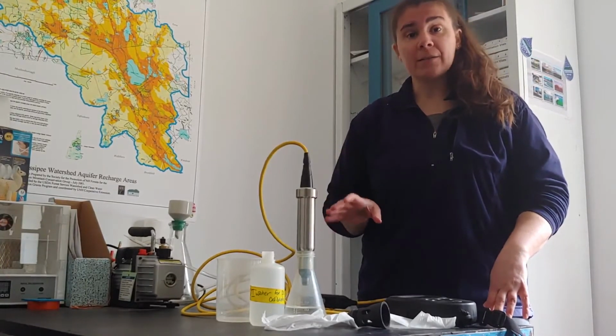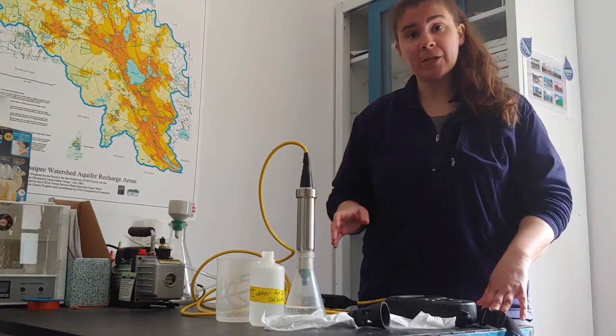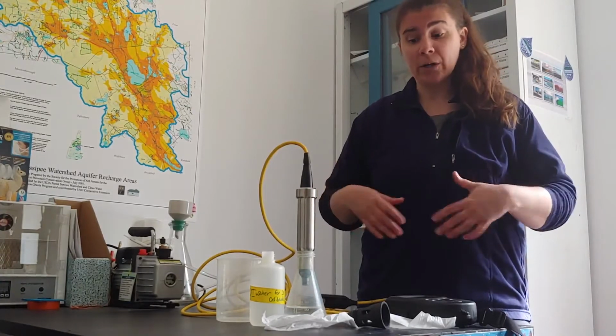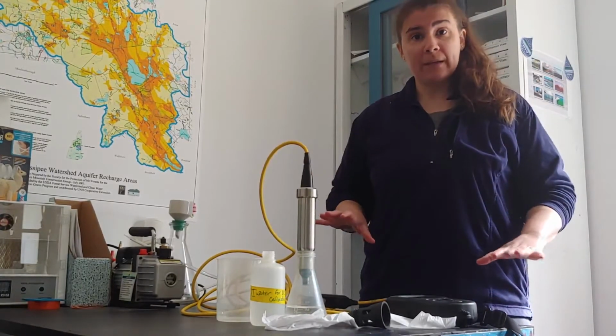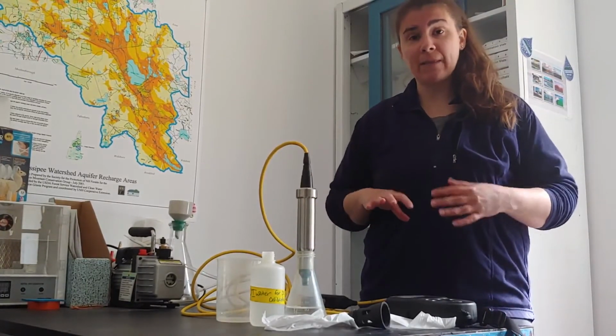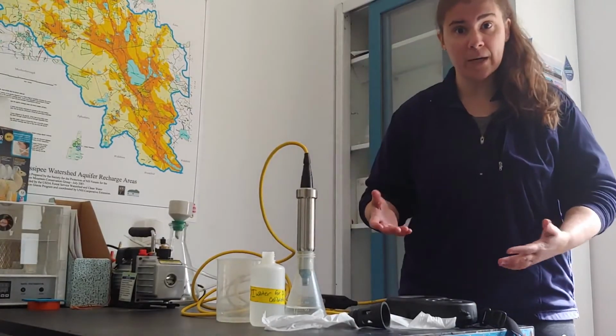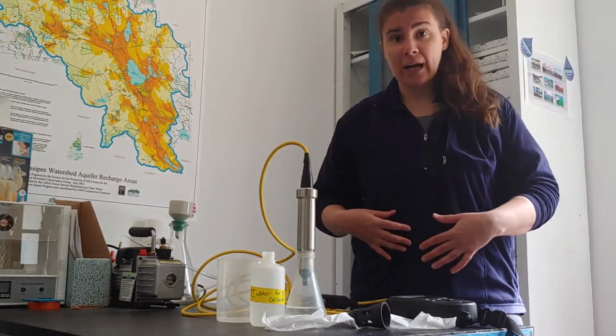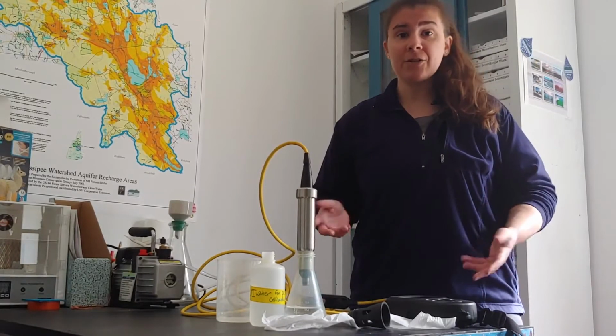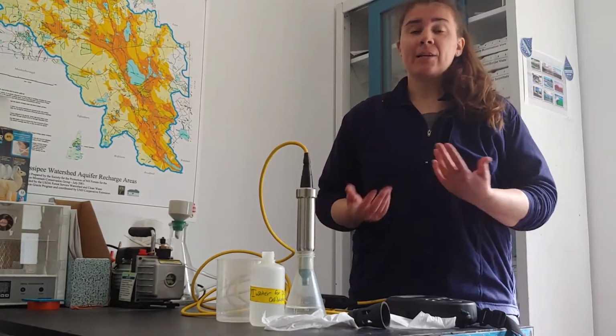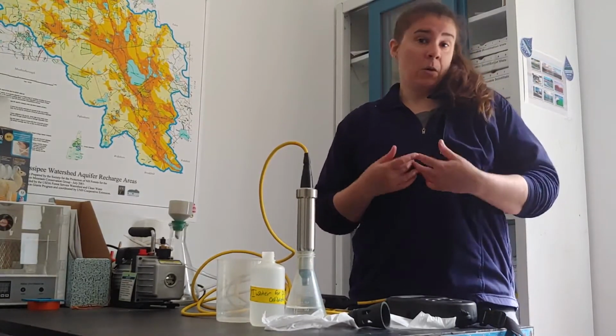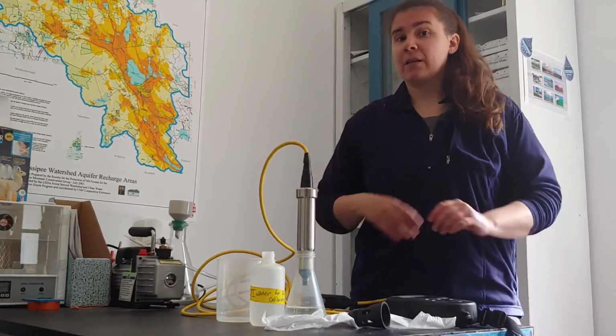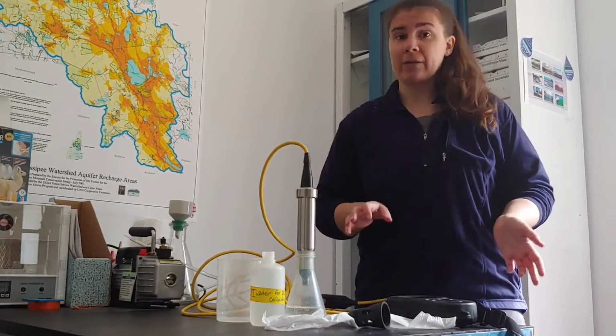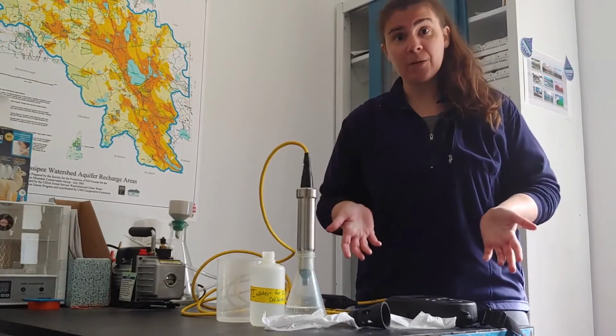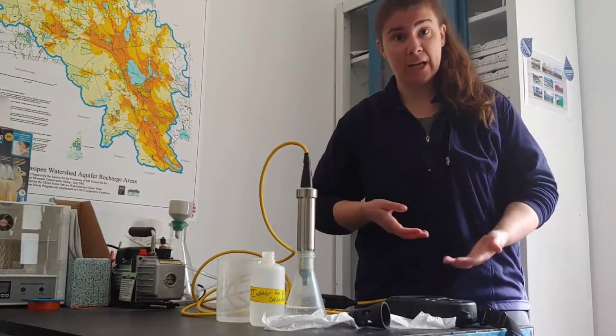A very important thing to keep in mind as you're doing this calibration is that it's easier and works faster if all the equipment is the same temperature. So we highly recommend that you do this calibration first thing in the morning. You bring the equipment into your house and you just calibrate it right in your kitchen or in your living room. I tell my volunteers a lot of times, just when you wake up, start your calibration and then go ahead and have your cup of coffee, eat your breakfast, brush your teeth, whatever it is you normally do in the morning, and then just keep coming back and checking on it.